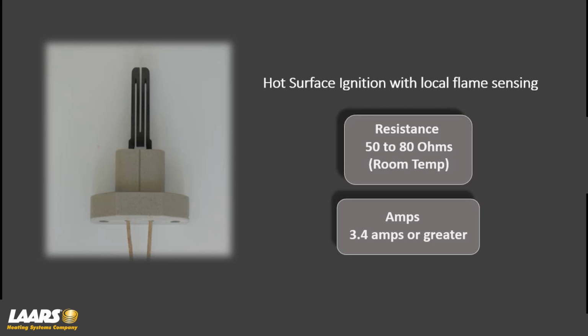And it's kind of a wear and tear item. Every manufacturer out there that makes this type of product uses hot surface ignition. So again, it's a wear and tear type item, short cycling, gas recirculation, corrosive materials, all of that can play havoc on anybody's ignition point. So keep that in mind. I did mention to you most of the service managers use amp probes. Let me give you another example. You go to a service call and maybe you have a bad pump. You can't fire the boiler, you have to order a pump. Well, while you're there, do a simple Ohms test on that igniter. Now you know if you need the pump, then you go to fire the boiler, all of a sudden now it doesn't work. Now you got to order a new igniter. Double check it at that point.